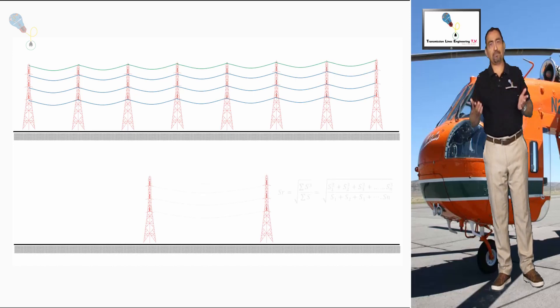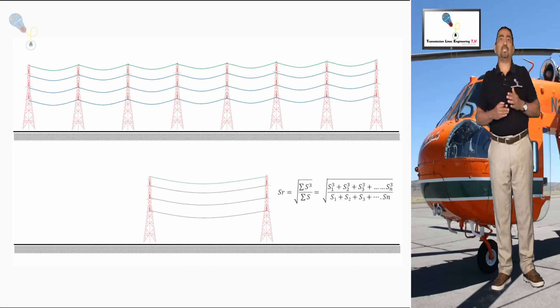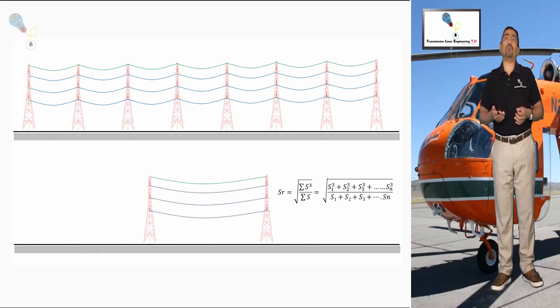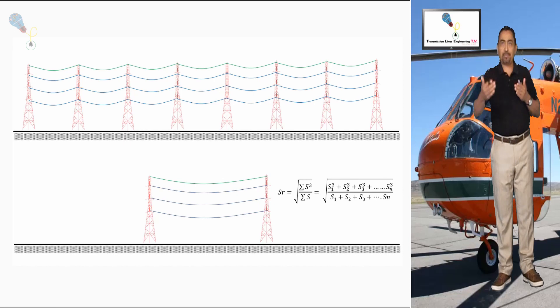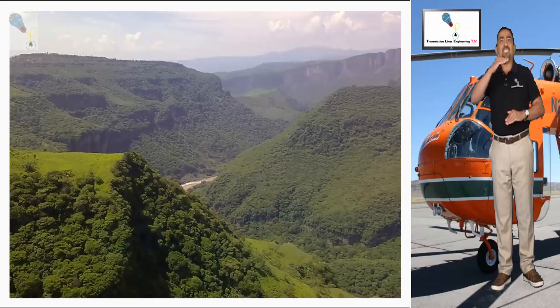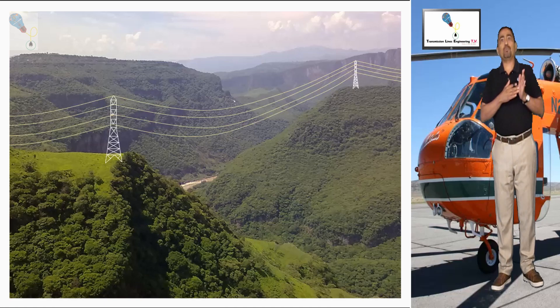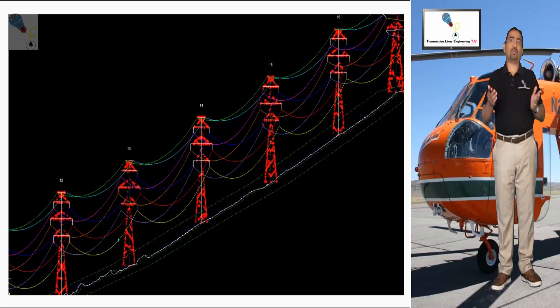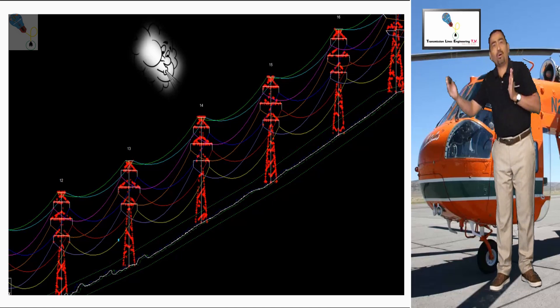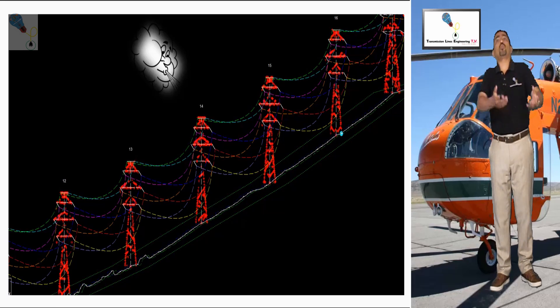Even though we have this ruling span, there will be smaller spans during the design of the line, and there will also be larger spans which are impossible to know in advance. The larger the span, with the same temperature, the larger the sag will be, and in turn the larger the horizontal swing, having as a consequence that under certain loading conditions the conductor swings will be beyond the limits of the right-of-way of the line. Therefore, it is good practice to add a percentage to the proposed ruling span in order to compensate for those spans which could exceed this value.